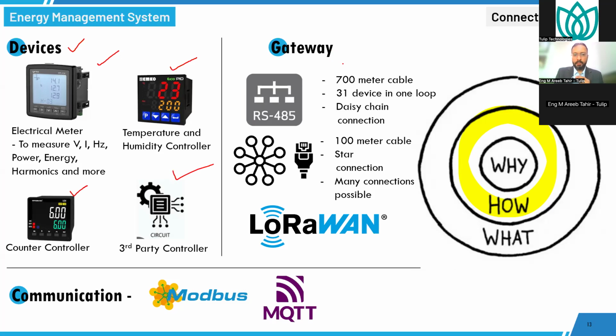Now, regarding the connectivity of the gateway, there are different options. For the physical layer, you can have RS-485. A single cable can run for 700 meters - a little less than a kilometer - and in one loop you can have 31 devices. If you have more devices, you can add another loop. This is a daisy chain connection.